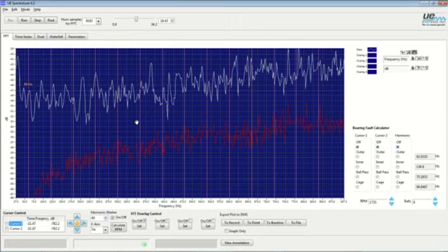As the discharges of energy begin to occur on top of that, we will lose or we'll see a reduction in the 60 Hz peaks on the outer part of the spectrum. And that's because on top of the stress on the negative half cycle, at other points on the electrical sine wave, you have these discharges occurring.